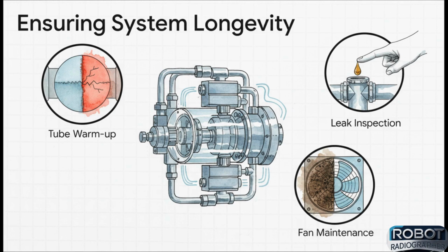And keeping this delicate thermal system in balance is an ongoing job. Operators have to run warm-up procedures to avoid cracking the anode with thermal shock. It's just like putting a cold glass dish straight into a blazing hot oven. They're constantly optimizing settings, inspecting for tiny oil leaks, and keeping the cooling fans clean. Every single step is about protecting that critical pathway for heat to escape.